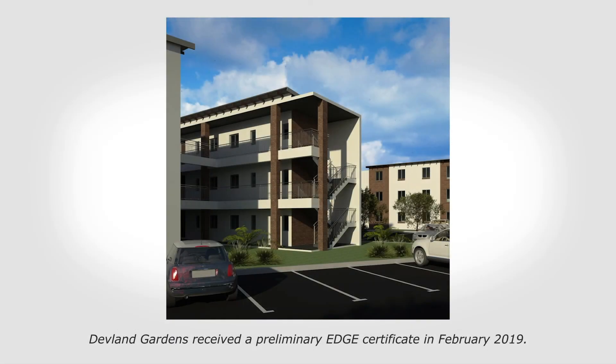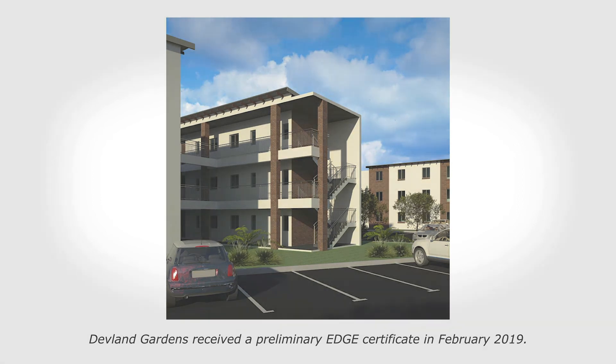In some cases, special considerations must be made. For example, if a wall is enclosing a balcony and has a large opening, that wall should not be added to the exterior wall calculations because the balcony is open to air. A good rule to follow is that the exterior walls that count for WWR are the walls that are separating the interior conditioned space from the outside air.